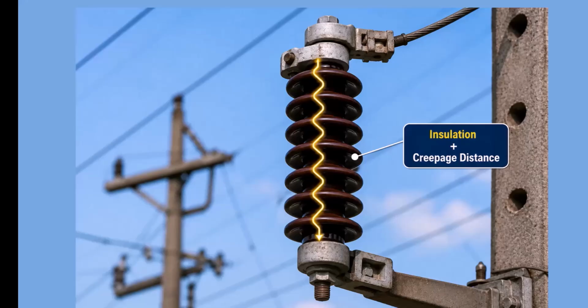And notice that the surface is not smooth. Those ribs increase the distance that leakage current would have to travel along the surface of the insulator. That should remind you of another concept, insulation and creepage distance. This becomes especially important when the surface is exposed to rain, dust, salt, pollution, or other contamination.